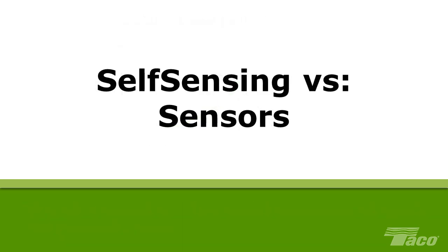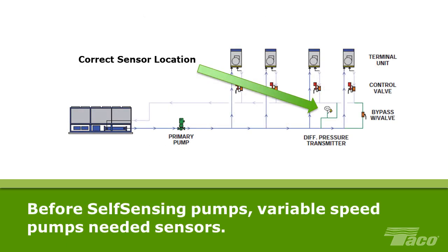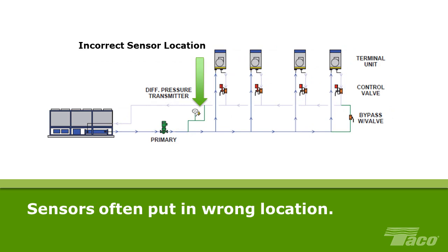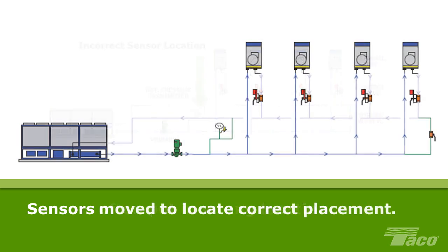Self-sensing versus sensors. Until self-sensing pumps were developed, variable speed pumps required sensors at various places in the system to provide the feedback to control their speed. However, in practice, using sensors for this purpose is plagued by many problems. Sensors are frequently placed in the wrong location in the system, and incorrect sensor placement results in system inefficiency. Typically, sensors must be physically moved from one location to the other, searching for the correct placement. This can be costly and is often impractical.